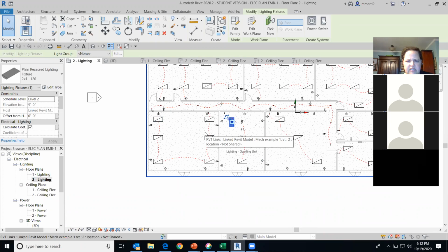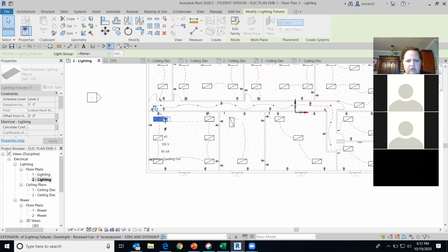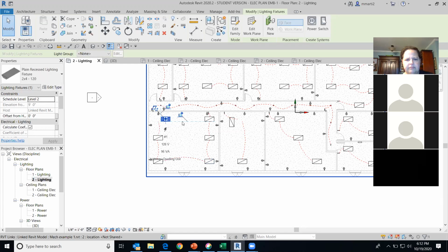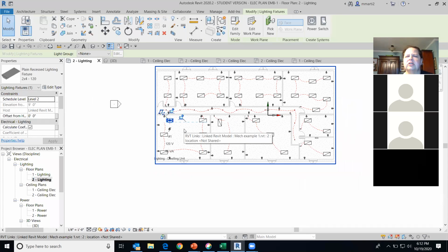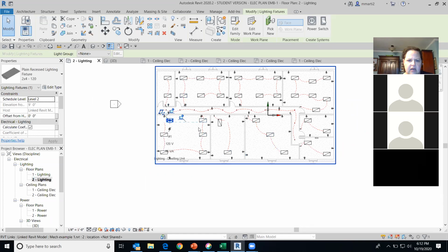The orientation of these lights is okay, but I'd move them closer in towards the center, because these walls are going to be washed out with that light, or you're going to possibly have a darker area in the middle. So we want to think about that even distribution of light at that point. So we just move these over a little bit. And you would have an electrician, a person that's familiar with lighting, review these, and this would be something that you would probably get a red line back. They would just highlight them on the drawing and send them back to you.